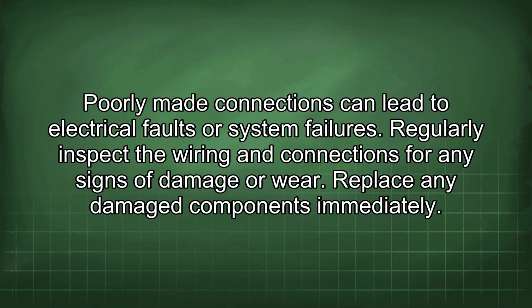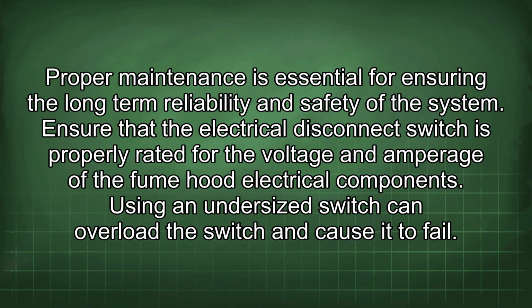Regularly inspect the wiring and connections for any signs of damage or wear. Replace any damaged components immediately. Proper maintenance is essential for ensuring the long-term reliability and safety of the system. Ensure that the electrical disconnect switch is properly rated for the voltage and amperage of the fume hood electrical components. Using an undersized switch can overload the switch and cause it to fail.